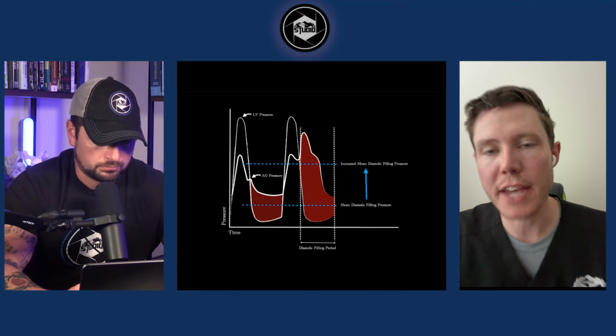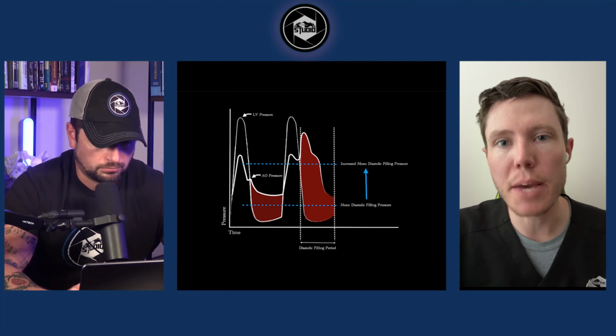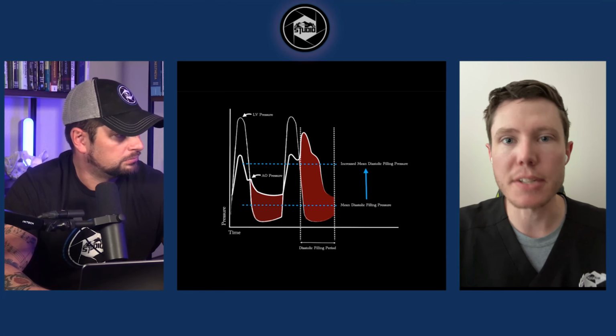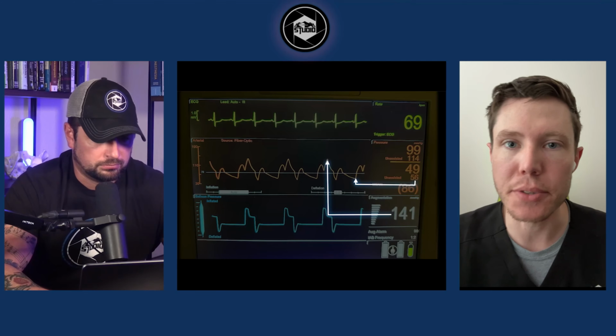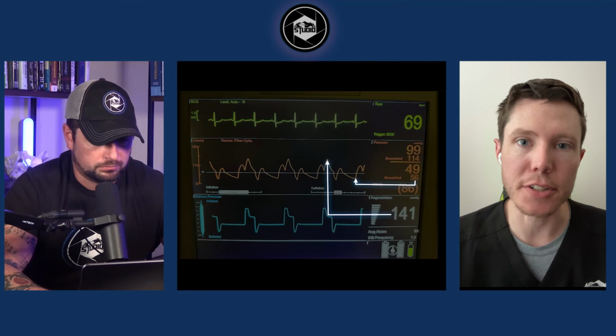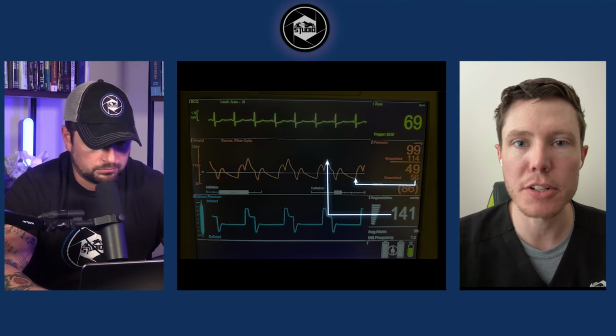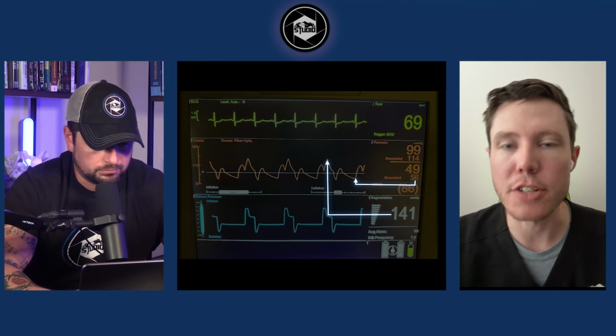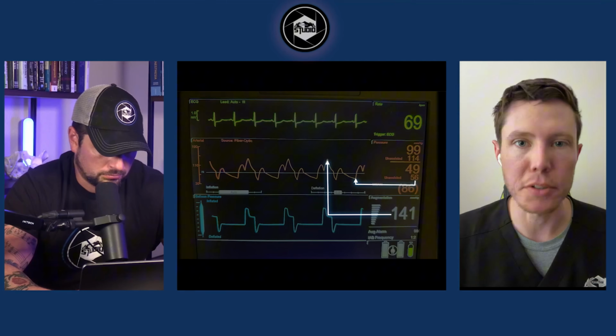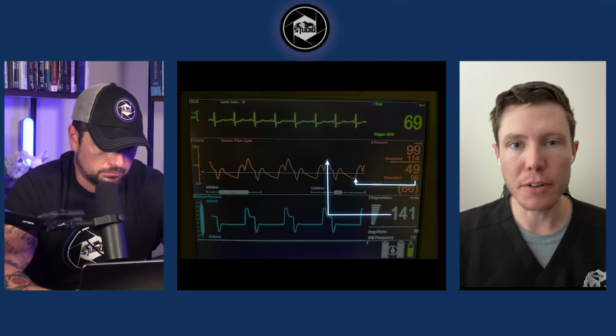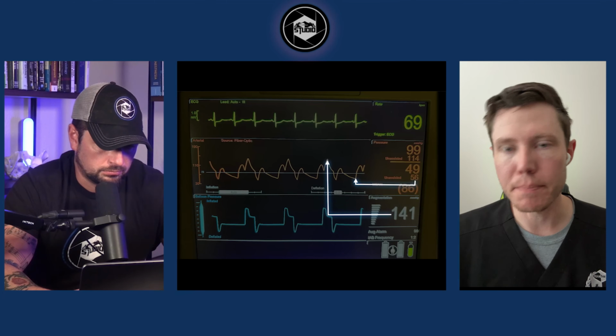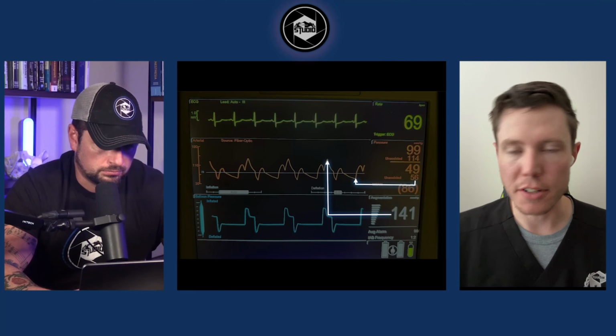Now, if that number climbs up into the 160s, 170s, something like that, then yeah, I do think that you might want to consider decreasing the augmentation a little bit. And generally, when balloon pumps are run, they're run at full augmentation. And what that means is that the balloon is inflating and deflating with its full volume of air. So it's a 50 cc balloon. It'll inflate and deflate with 50 cc's of helium. If it's a 40 cc, et cetera, same thing.